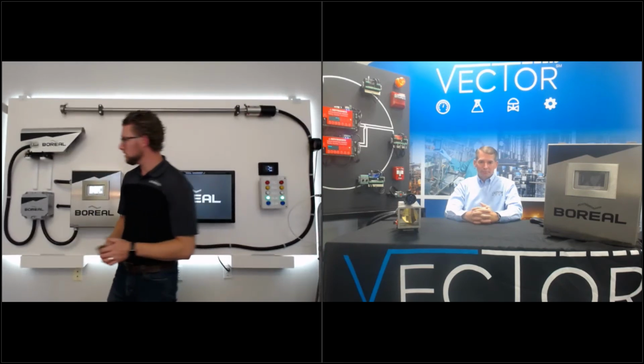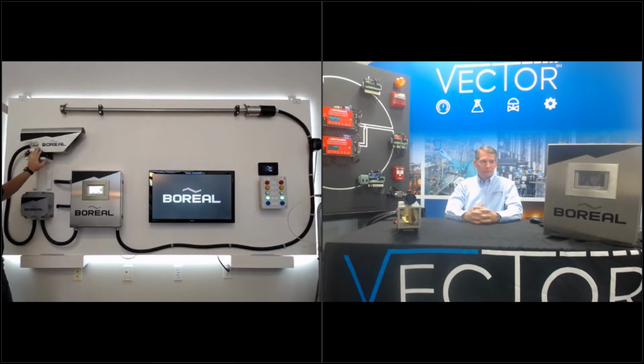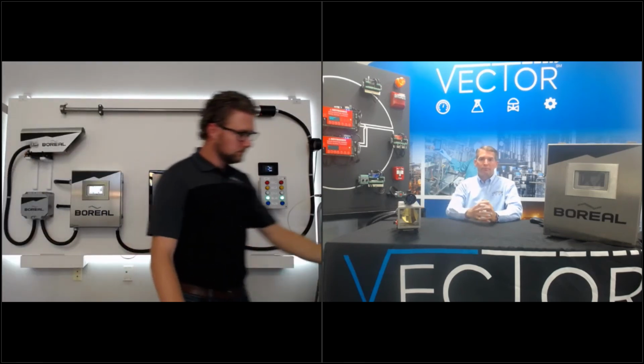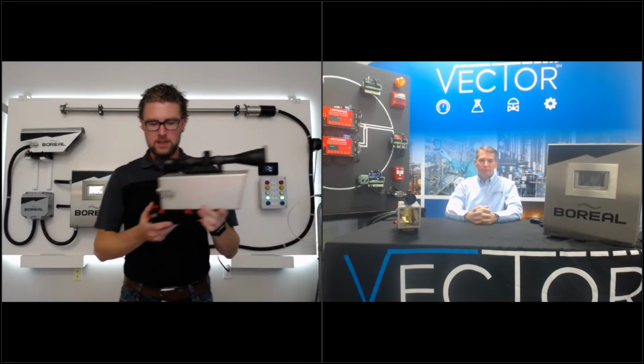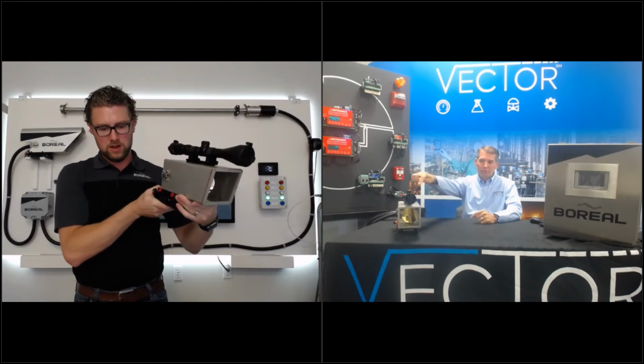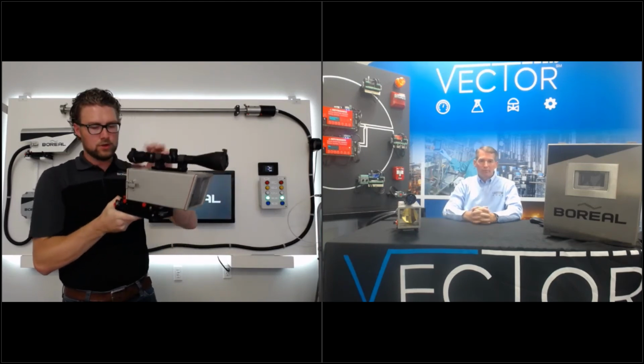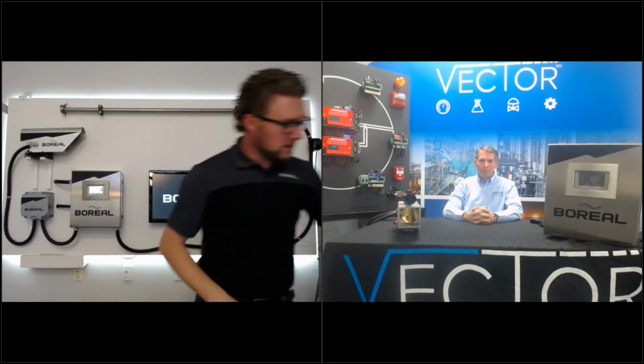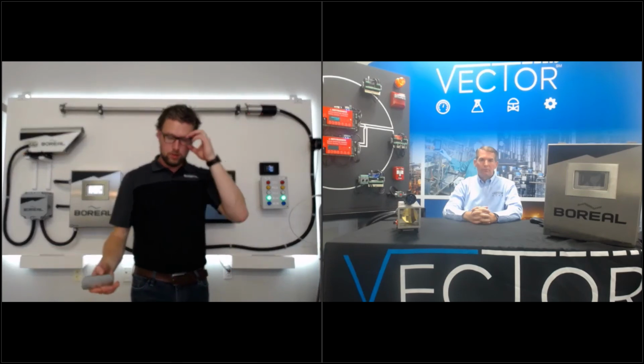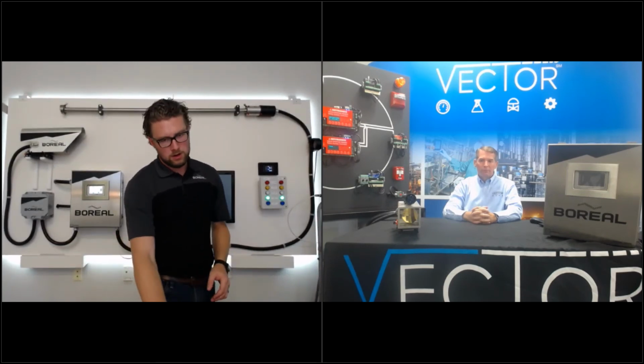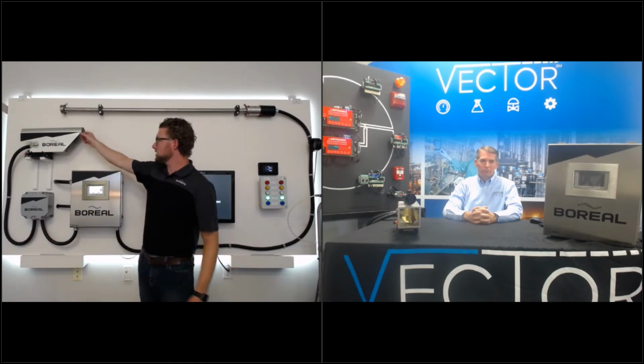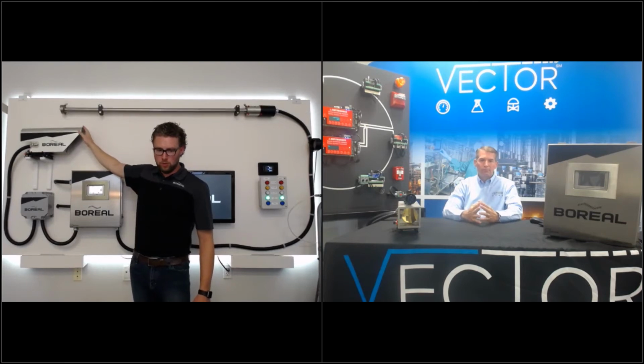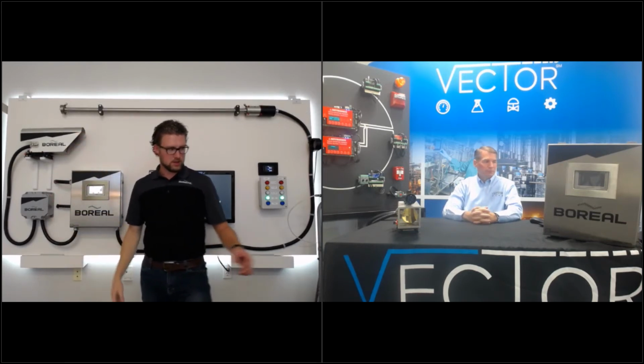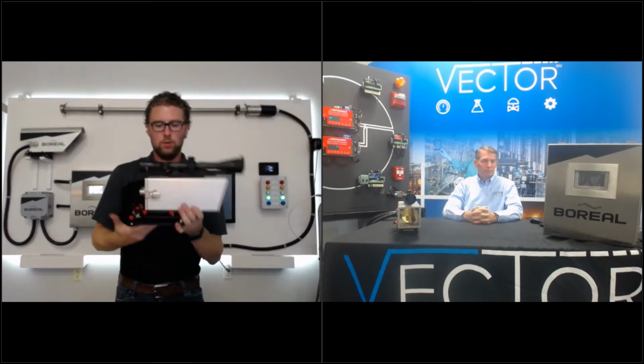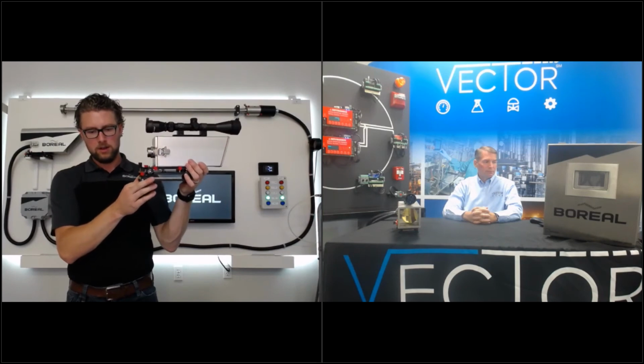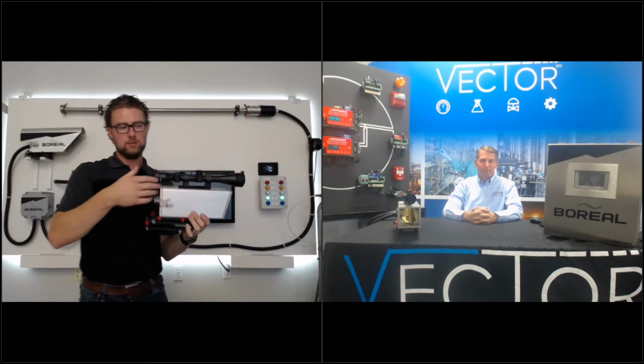A rough rule of thumb is if we were to stand at the transceiver and look at the retroreflector, for example, our transceiver configurations come with a rifle scope mounted on top for easy optical alignment. Even looking through the rifle scope at maximum power or zoom, as long as you can see the retroreflector, the system will still work and function. So dirty optics are not as much of an issue as one may think. There is a rain and dust hood that cowls over the open path head here that does a very good job of keeping dirt, dust, and debris from building on the windows. The window of our open path head is slightly angled, another simple engineering fix to keep items from coating the windows.